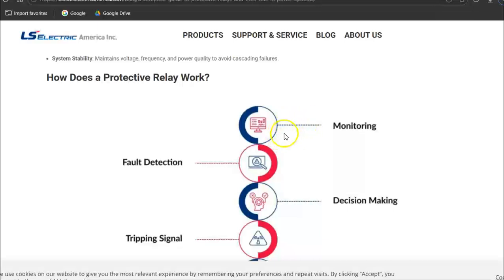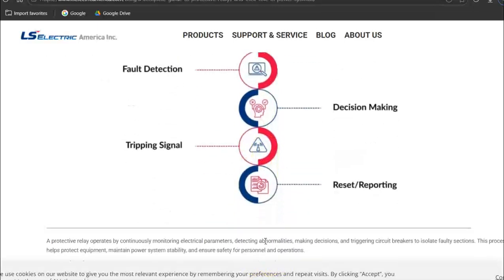How do they work? Well, a protective relay comes in many sizes and shapes. It's a pretty generic name. So they monitor something. They monitor current using CTs. They monitor the voltage using PTs. They can monitor the frequency by looking at the exact frequency, 60 hertz. And then they have thresholds that they would acknowledge and look at. This has exceeded some threshold. So the current's too high, the voltage is too low, there's a voltage dropout or a voltage spike. And then the logic finds out that this is now an abnormal situation. It's exceeded the thresholds that have been set, exceeded the limits, and therefore it signals a trip action on its output, and that would open a breaker.